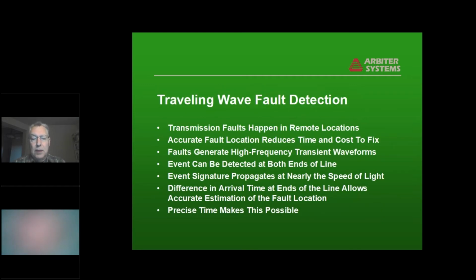Traveling wave fault detection. Well, you know that transmission faults not only happen in remote locations, they always happen in the most inconvenient remote location, expensive to get to, flying out a crew on a helicopter or whatever. So knowing where the fault is greatly minimizes the cost and time to remediate that failure. And what happens when there's a fault is that when lightning hits the line or the line hits a tree or whatever, the high frequency signals are imposed on the line due to those currents. And that can be detected at the end of the line by looking at the current artifacts traveling back on the line. And that event signature propagates at whatever the propagation velocity is on that line.